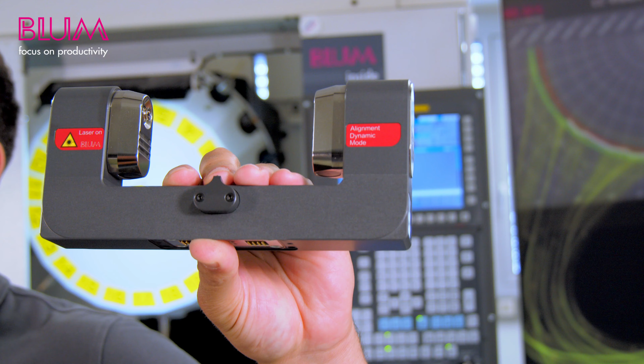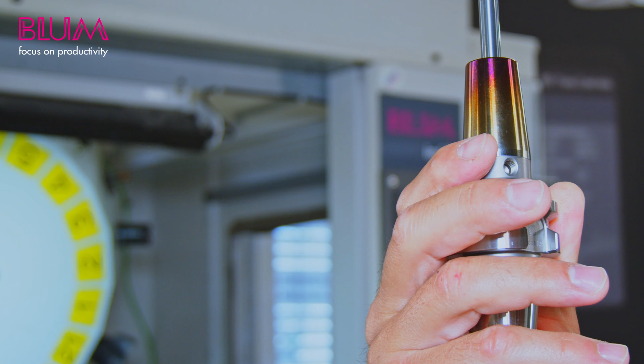What do you need for this? Your laser, of course, and a reference tool for calibration. What happens during calibration? To put it simply, we use our reference tool to accurately determine the precise switching points of our laser. The determined switching points are then stored fully automatically in the cycle, in the corresponding parameters, and are used again for measurement.